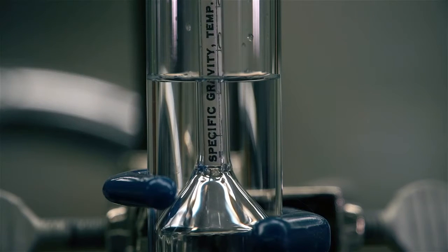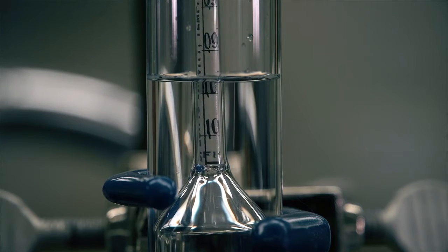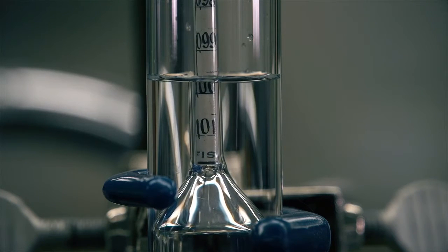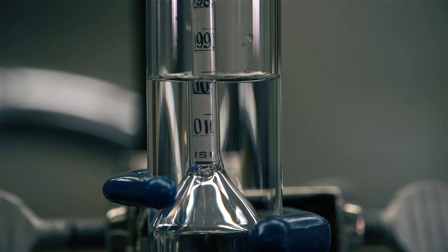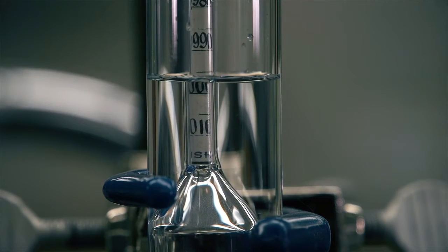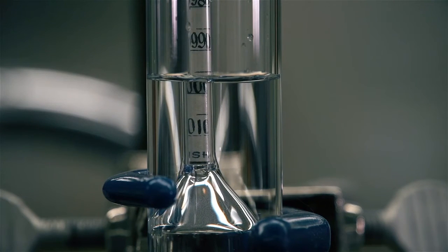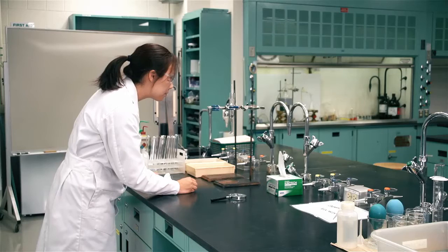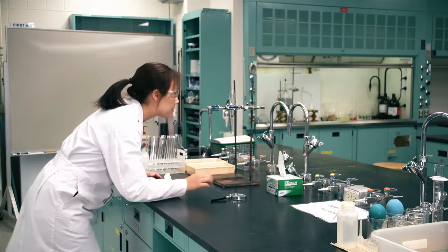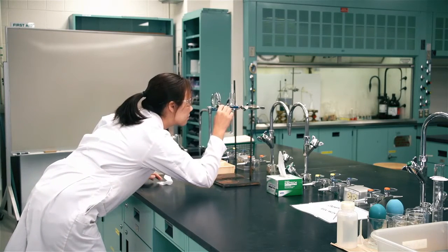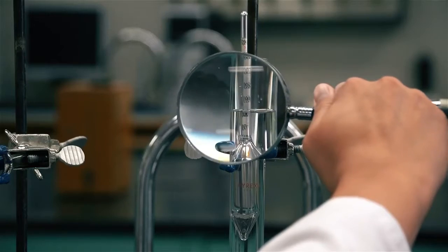away from the walls of the test tube and to remove any trapped gas bubbles under it. Keep the rest of the stem dry, as unnecessary liquid on the stem changes the effective weight of the instrument and affects the readings obtained.